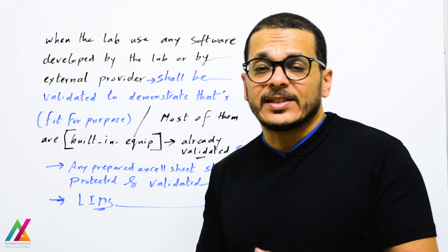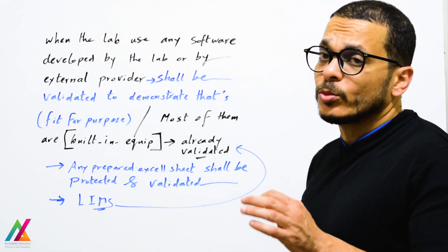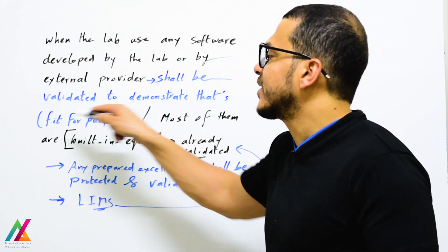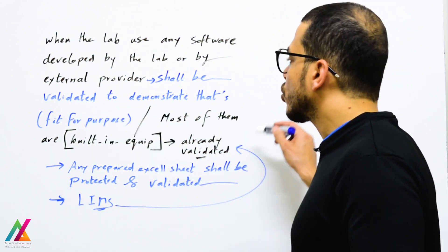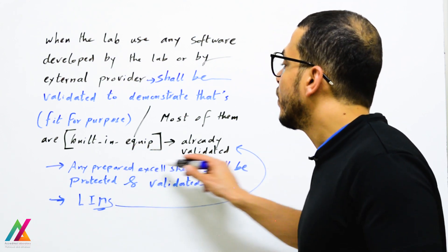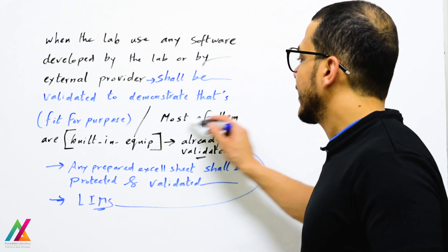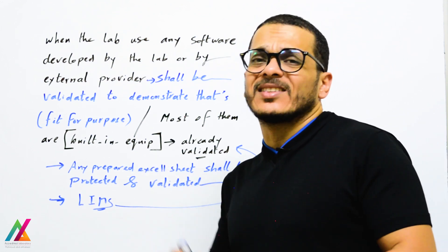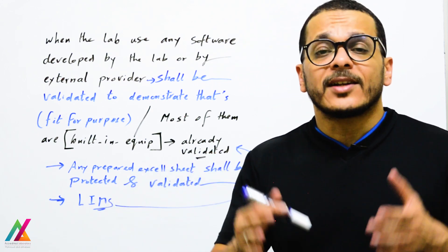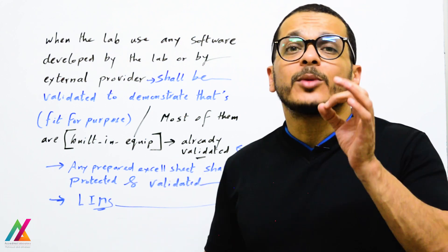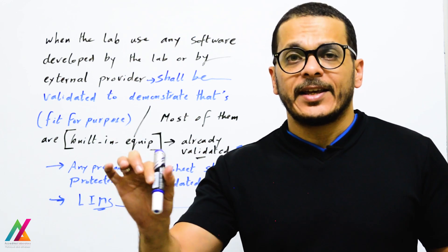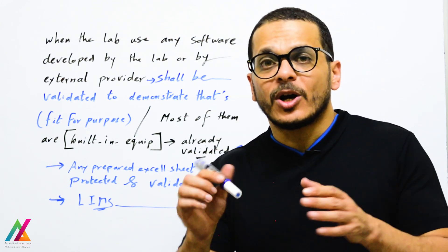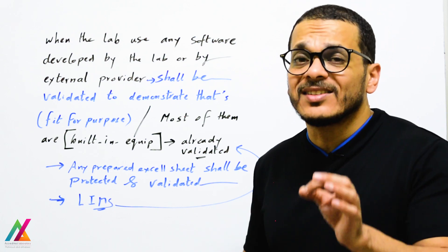All equipment inside the lab shall be labeled to prevent misuse, based on the risk-based approach. Software is now considered equipment and shall be validated like any other equipment. When the lab uses software developed internally or by an external provider, it shall be validated to demonstrate it is fit for purpose. Most software inside the lab is built into the instrument and already validated by the provider. Any prepared Excel sheet shall be protected by password — if an assessor clicks on a cell during an audit, they should not be able to modify it. All Excel sheets shall be protected and validated.